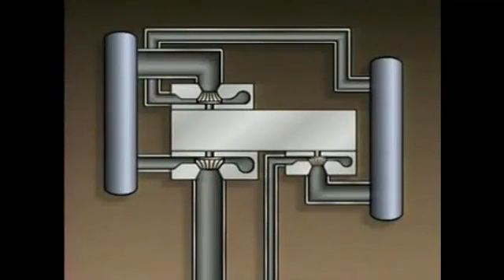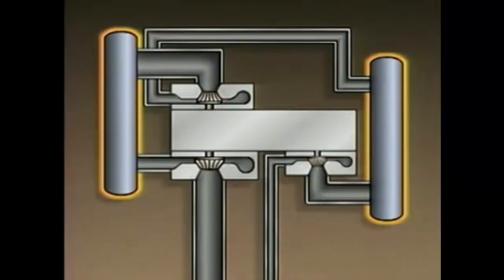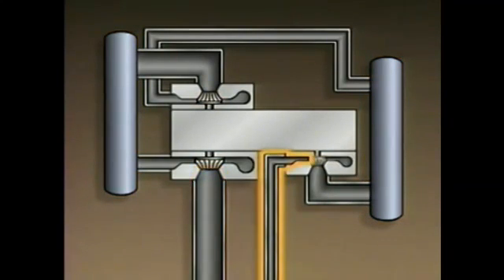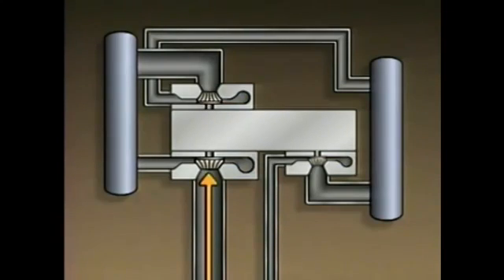In systems that require higher discharge pressures, multi-stage centrifugal compressors are typically used. This simplified illustration is a top view of a multi-stage centrifugal compressor. The compressor has three impellers, two intercoolers, a suction line, and a discharge line. There is a volute associated with each impeller. During operation, gas enters through the suction line into the first impeller. The gas passes through this impeller and the associated volute where its pressure is increased.